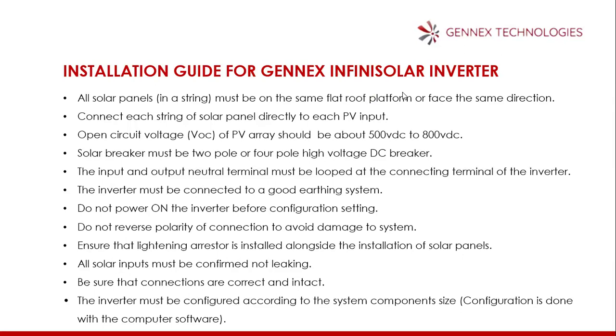Also, ensure that lightning arrestor is installed alongside the installation of solar panels on the roof. All solar inputs must be confirmed not leaking. Be sure that connections are correct and intact. The inverter must be configured according to the system component size. Configuration is done with the computer software.